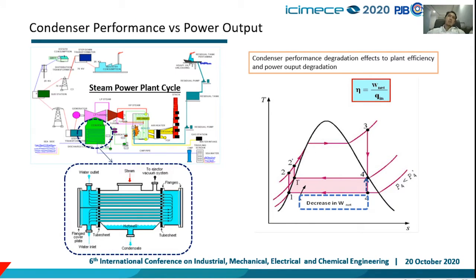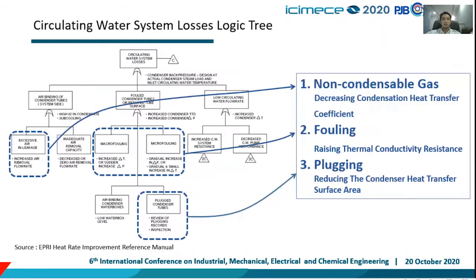A condenser is one of the main equipment in a steam power plant that functions to condense turbine exhaust steam using a cooling medium in the form of circulating water from seawater or river water. Condenser performance degradation affects plant efficiency and power output. There are several factors that can cause condenser performance degradation; three of them are Non-Condensable Gas, Fouling, and Plugging.